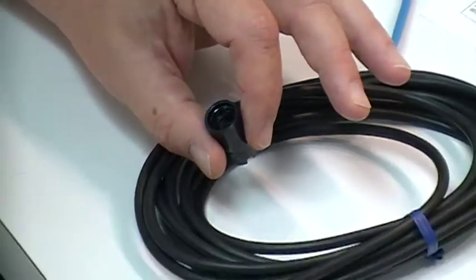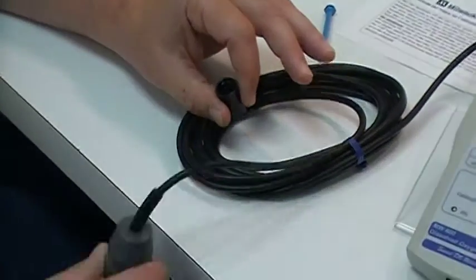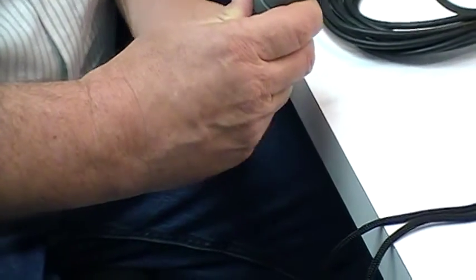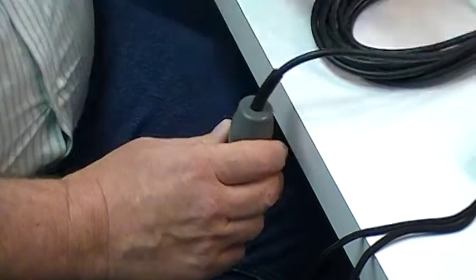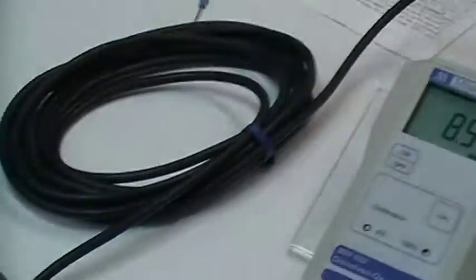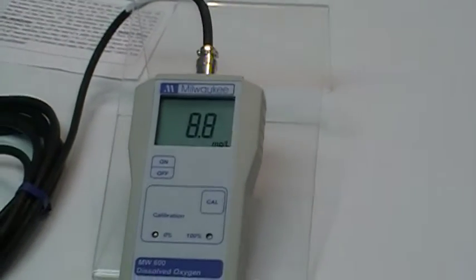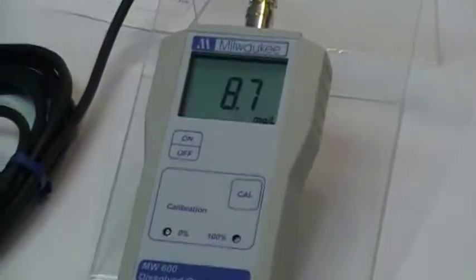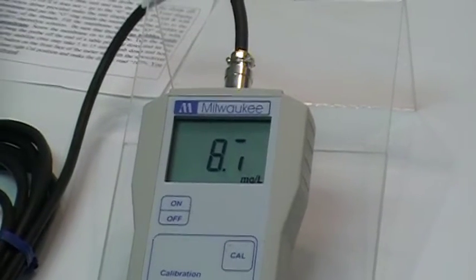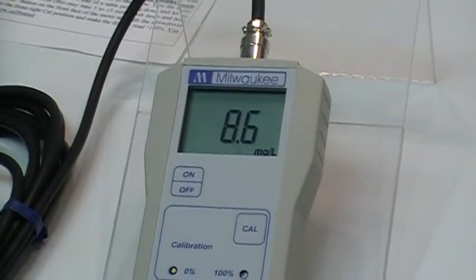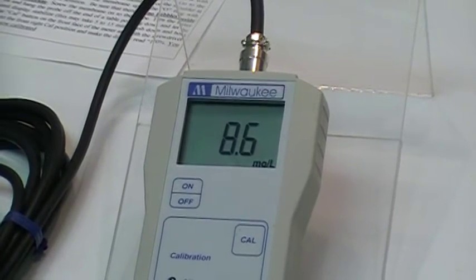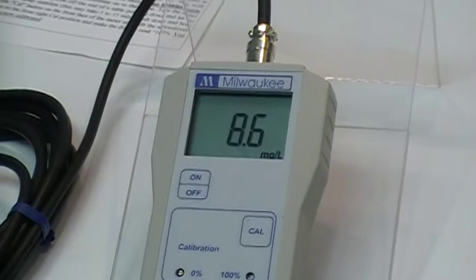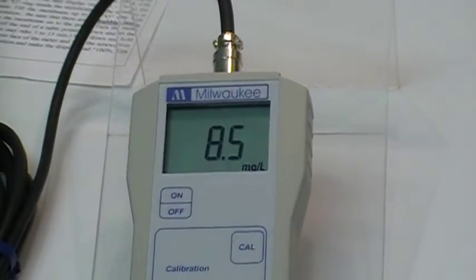So once we've established that there are no air bubbles inside the electrolyte, take your probe and just put it onto the bottom and hand tighten the membrane onto the probe, and then let it hang back off the table. As you can see, the numbers are starting to fall on the display. They will continue to fall as the electrolyte that's inside the membrane continues to take a charge. And that's what we're doing, charging up the electrolyte that's inside this membrane. Usually this procedure will take between 5 and 10 minutes to stabilize. We recommend giving it a minimum of 5 minutes before it is stabilized.